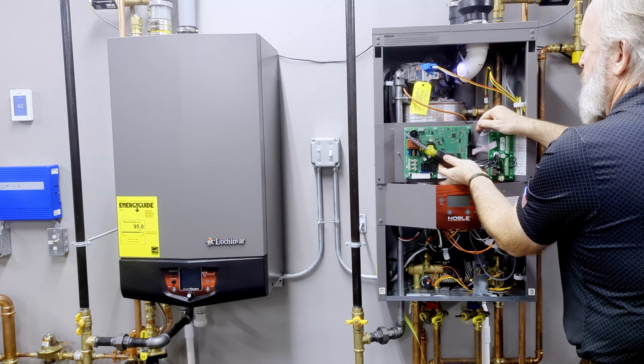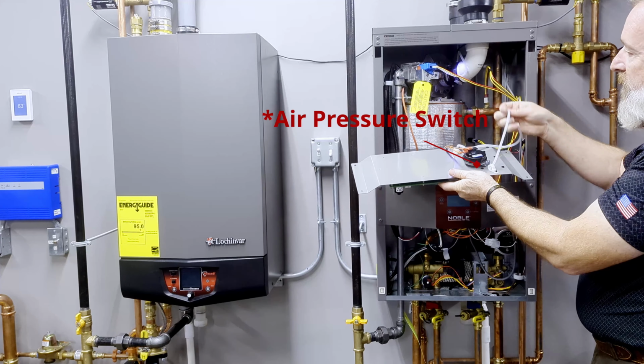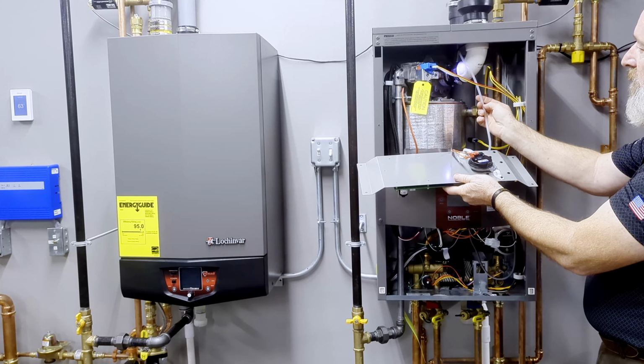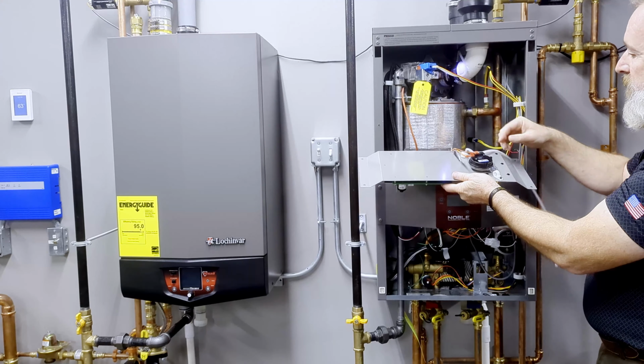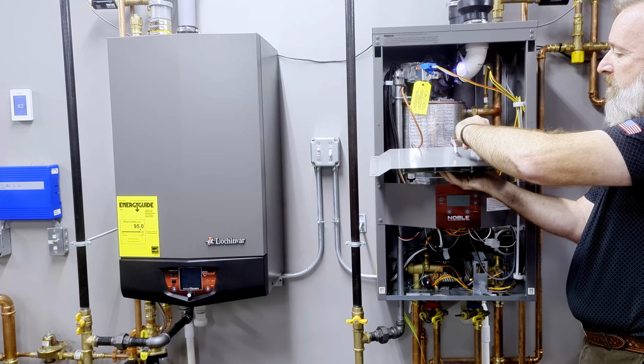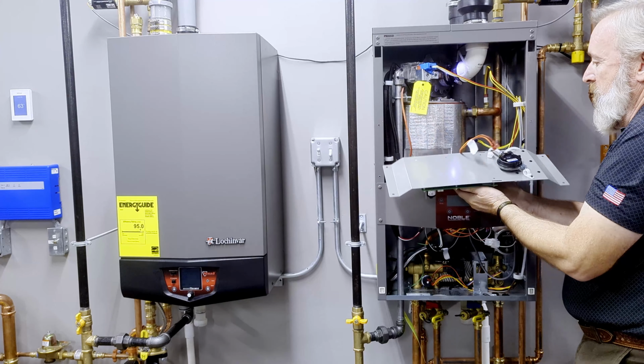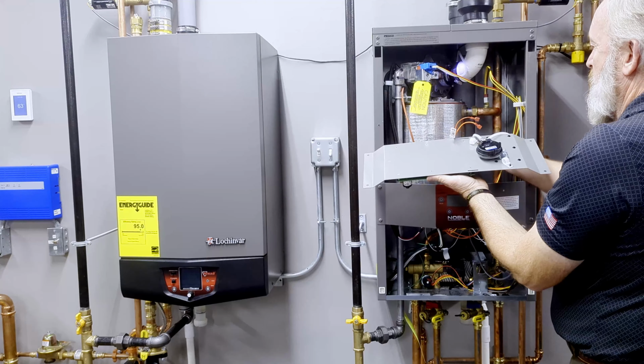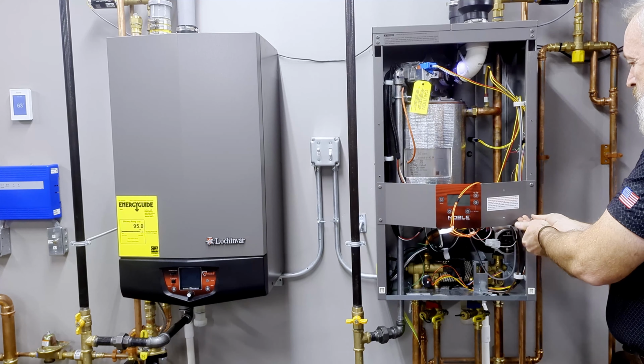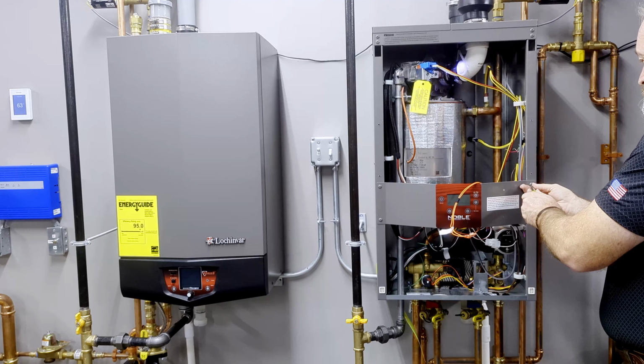Now the back side of this board is the low pressure switch. There are going to be 2 hoses. One runs up to a T that goes to the gas valve, and the second one runs over to the flue. You'll also find there are 2 orange wires. These are your safety circuit for the low pressure switch. Sometimes these can be a little tough to get off of there. Once that's removed, we're going to go ahead and take the lower panel off.